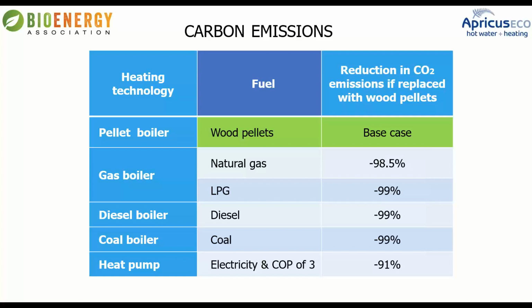We have some fossil fuel and emissions embedded in our electricity grid, albeit a really renewable grid. But because of the incredibly low impact of wood pellets, even a heat pump with a coefficient of performance of 3 — meaning you get 3 times as much heat energy out as electricity in — it's still a 91% reduction in carbon intensity when you use a pellet boiler in place of a heat pump. So it's not to say a heat pump hasn't got a place, but it's not quite as clear cut from a carbon perspective as maybe indicated sometimes.